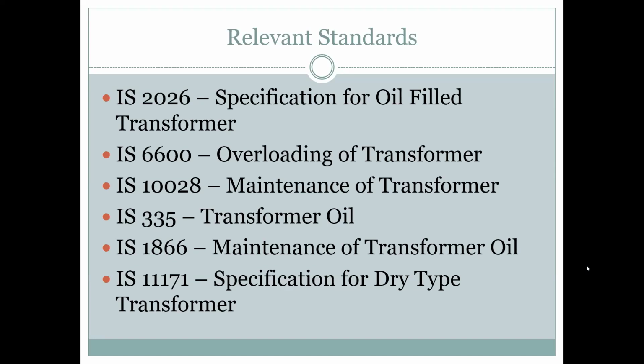Now, breakdown voltage. Transformer oil serves two purposes. The first purpose is cooling. Definitely, it takes the heat generated in the winding, absorbs the heat, goes to the radiator, and gets dissipated by the natural phenomenon of convection, and cold oil goes back in. So this circulation is going on. But it also serves one more purpose, that is insulation. So transformer oil is the most interesting subject by itself. That's why there are two distinct standards. IS 1866 is the maintenance of transformer oil, how to maintain transformer oil. It is a separate IS for that.